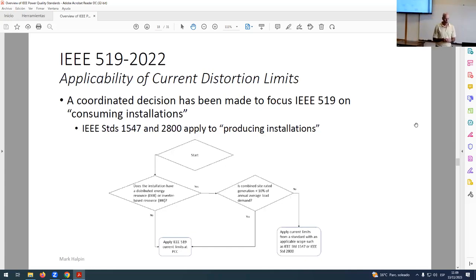You may know that historically, 519 has been intended to apply to consuming installations. 519 has been around since 1992. All right. In 1992, we didn't have to think too much about generating equipment producing harmonics. A synchronous machine doesn't produce very many harmonics. Okay? That's not true anymore. Now we've got all kinds of generating technology that produces all kinds of harmonics. Do the limits in IEEE 519 apply, for example, to a PWM inverter? Well, probably not, but that was all we had for a long time.